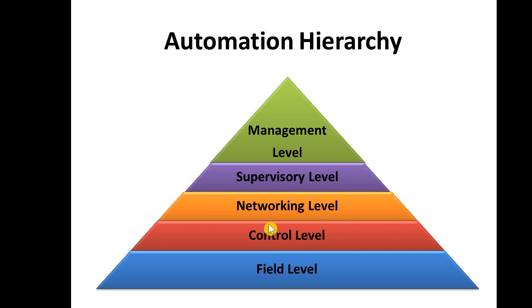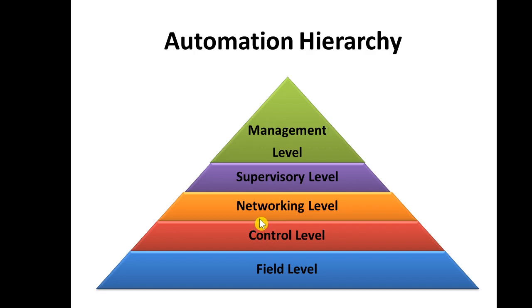The next level is the networking level. The networking level connects the control level and the supervisory level. It transfers data from the control level — from the PLC, PAC, or embedded system — up to the supervisory level. This may use Ethernet protocols or other industrial protocols like Modbus, Profibus, DeviceNet, or ControlNet.